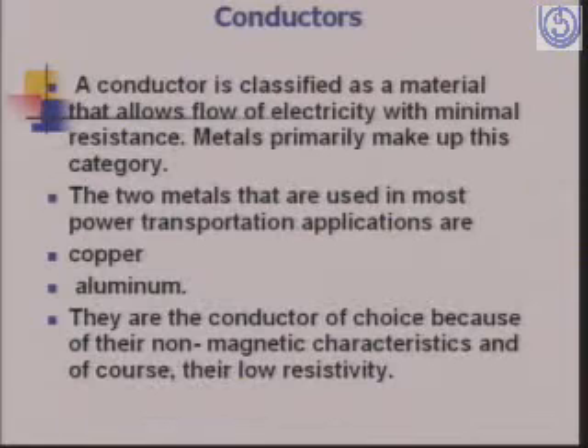Then we have the conductors, that is the main part of the line. And the conductor, as we also talked about earlier, is that which allows the flow of electricity. It is through the conductor that all the supporting equipment is for the conductor. And these conductors may be of copper or aluminium, these materials are the conductor of choice because of their non-magnetic characteristics and their low resistivity. And we talked about conductors like we have all aluminium conductor, triple AC conductor, and the ACSR conductor in the morning session.